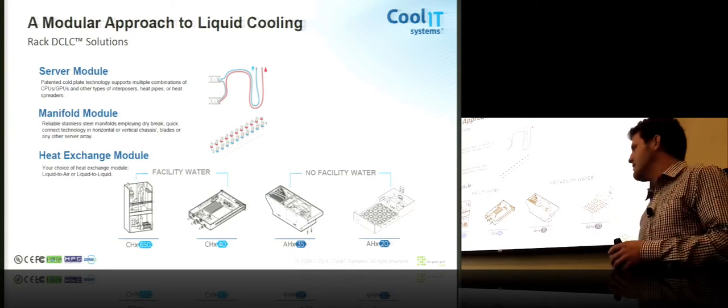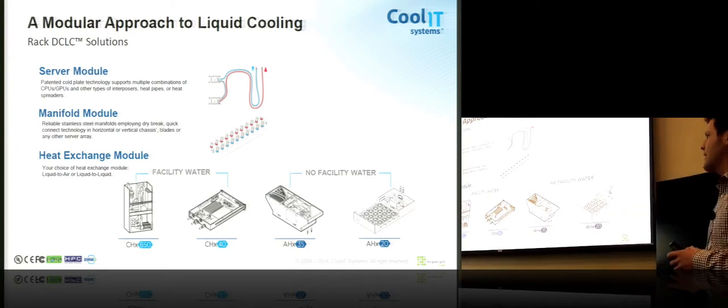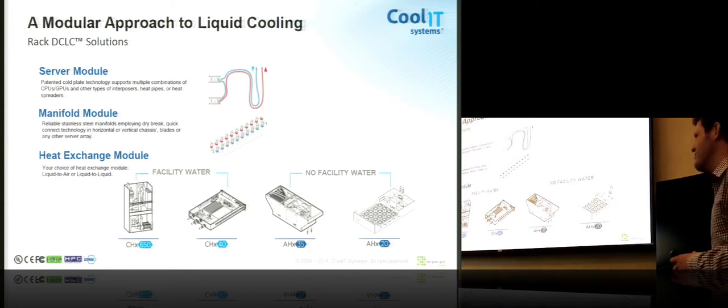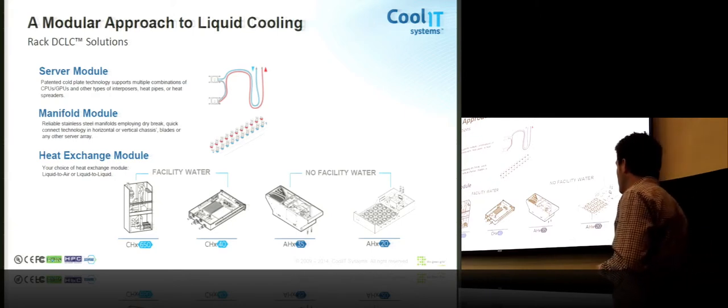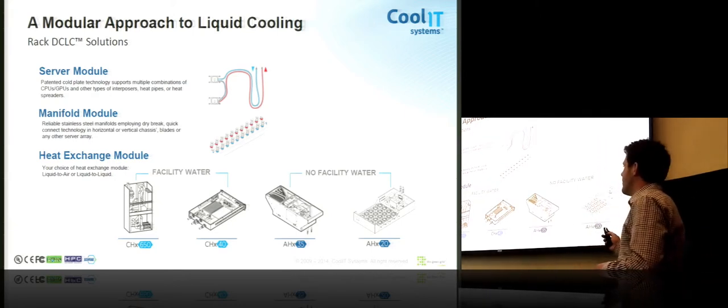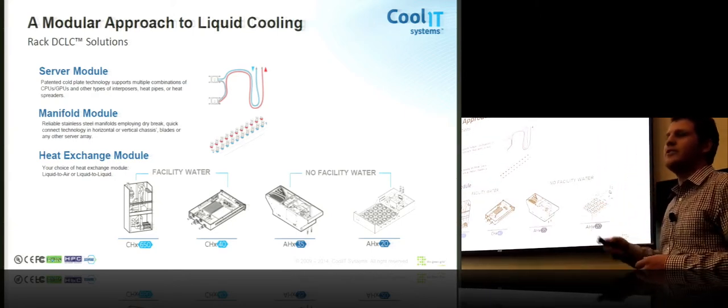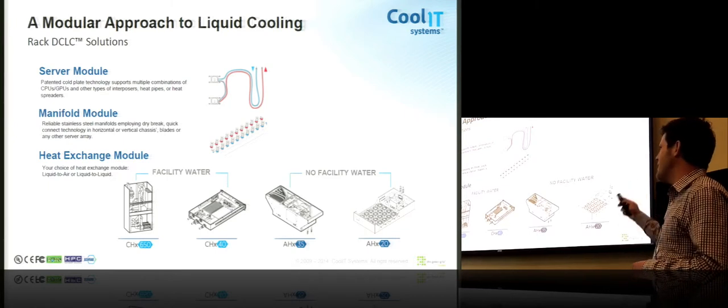The CHX650, on the other hand, is a row-based cooler. So it can handle 650 kilowatts. You can split that up into roughly 600 nodes, and you can put that in as many or as little racks as you'd like. So most of the numbers that I rattle off later are all based on our liquid-to-liquid heat exchanger, not the liquid-to-air.